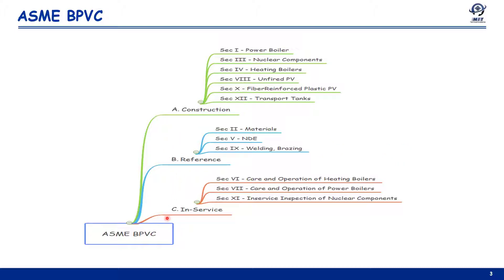Finally, in-service codes, which are also called care and operation codes: Section 6 covers care and operation of heating boilers, Section 7 for care and operation of power boilers, and Section 11 for in-service inspection of nuclear components.